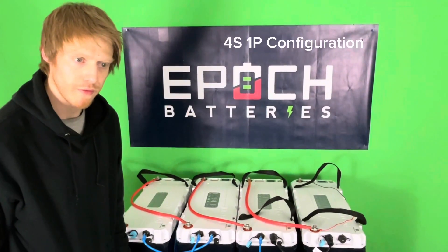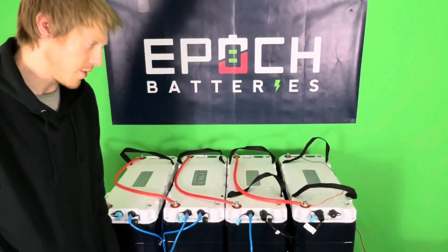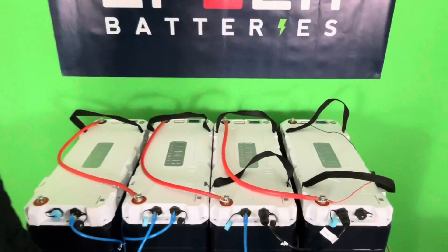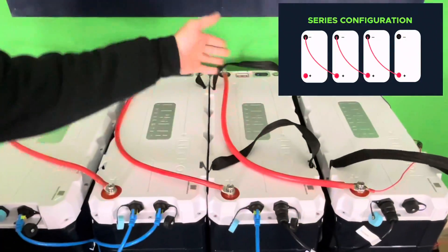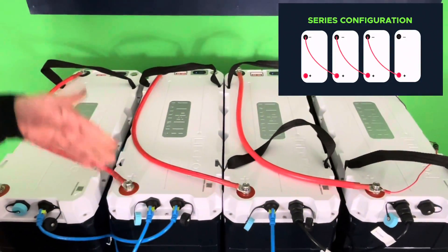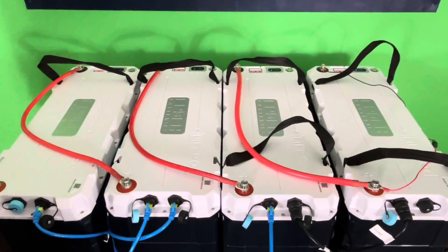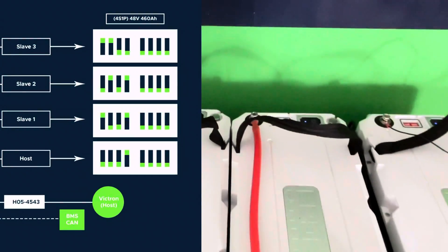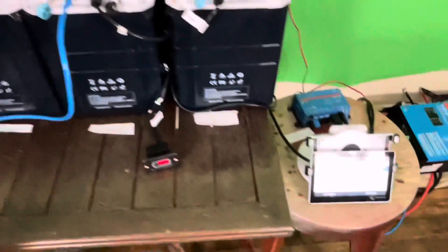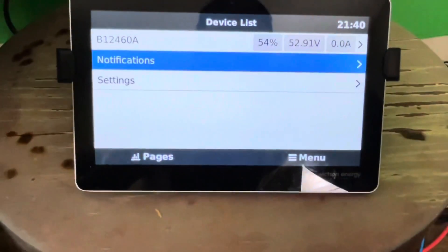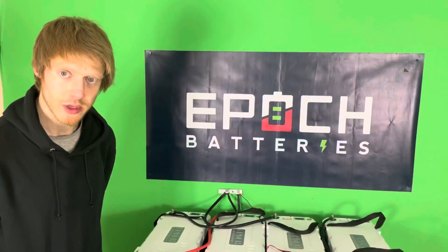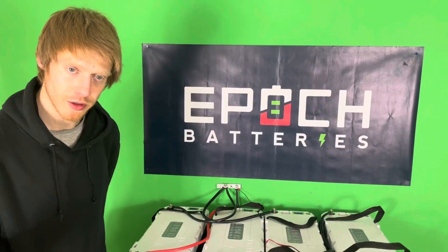Alright, so starting with the 4S1P configuration for a 48-volt 460 amp-hour, we're going to go from positive to negative, positive to negative. And as we've shown you, the dip switch settings, we'll display them here on the Cerbo, and you can see that we have our 52.9 volts. So that's all for this configuration and now on to the next.